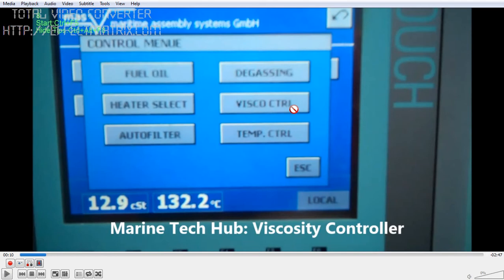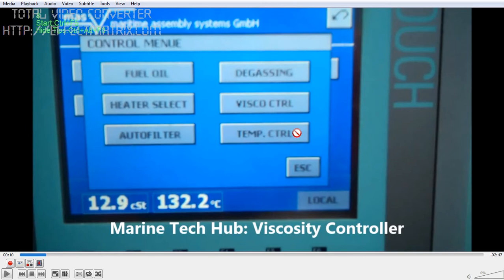The viscosity sensor gives a signal to the steam valve to control steam and maintain the viscosity — that is one part. Suppose the viscosity control is not working, then you can choose temperature control. Temperature control will open and close the steam in order to maintain the viscosity. You know that at a particular temperature the viscosity will be a certain value, so you try to maintain the temperature.